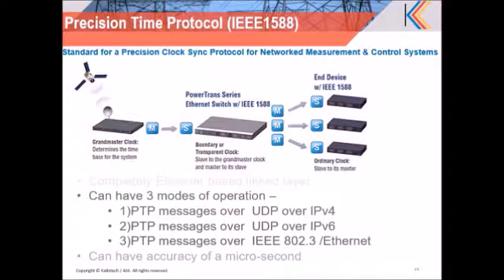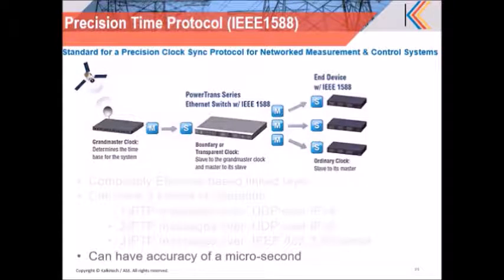There can be three methods of operation: one is UDP over IPv4, another is UDP over IPv6, and the third is PTP messages over Ethernet. With any of these scenarios, provided the device supports it, you can achieve synchronization, with accuracy up to the microsecond level. That is a speciality of the IEEE 1588 protocol that is introduced as part of the edition 2 standard.